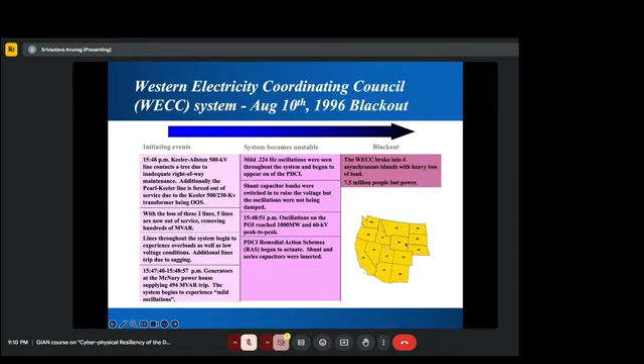Typically it takes two lines going out, because for a single line we should already be prepared. That then results in multiple things going out - generators trip, more lines go out. There will be some signature to look for, like oscillations, if you have real-time monitoring. The oscillation reaches a peak. If you detect this early, you can take proper, good control action, which will avoid the blackout - otherwise it will happen.